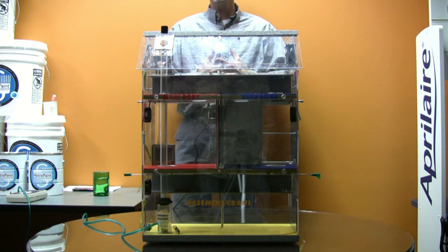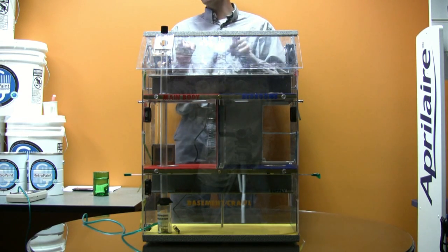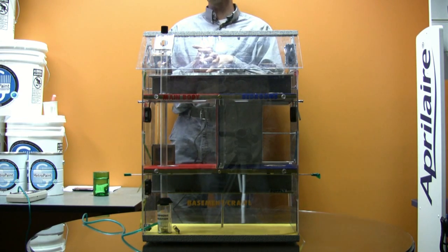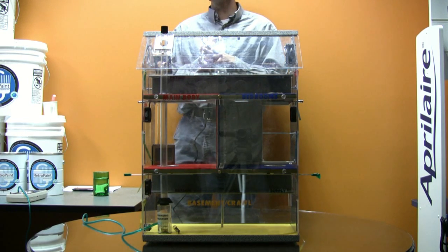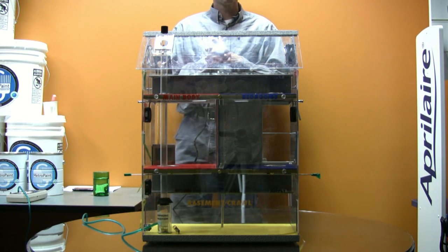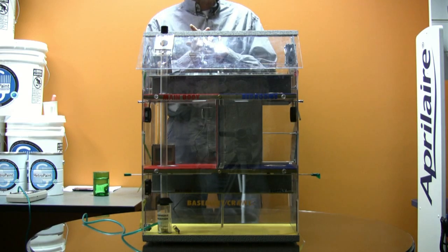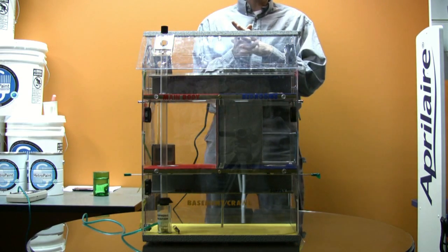What we're simulating right now is what's the worst possible case for that water heater before it turns on? How can we depressurize the basement to its absolute maximum? Seal up the door. Well, sealing up a door may or may not make it worse.